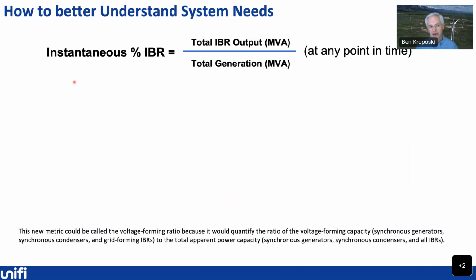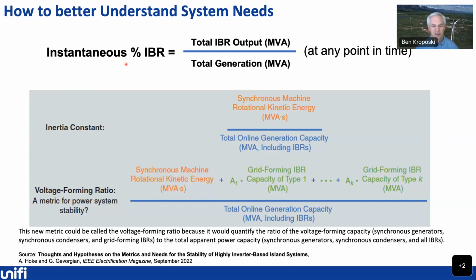Another way to think about the power system and what I just showed you there was instantaneous penetration levels of inverter-based resources, where you just divide the total amount of inverter-based resource by the total generation. That gives you that instantaneous level. The challenge with this number is it isn't very exact, and it doesn't tell you things like grid forming capability. So we've been looking at a variety of different ways of evaluating this, moving on from a single number to maybe something that looks like an inertia constant.